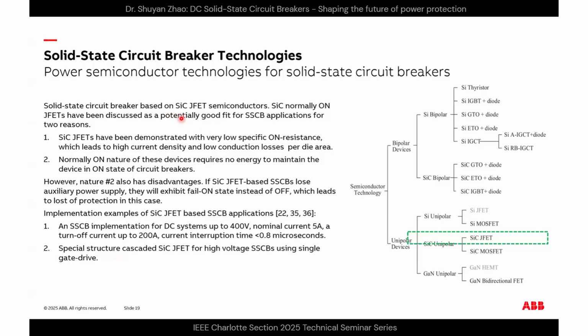Solid state breakers based on SiC JFET devices: these JFETs are normally-on devices, and this has been discussed as a potential good fit for solid state breaker applications for two reasons. JFETs have been demonstrated with very low specific on-state resistance, which leads to high current density and low conduction losses per die area. The normally-on nature of these devices requires no energy to maintain the device in the on-state of the breaker.